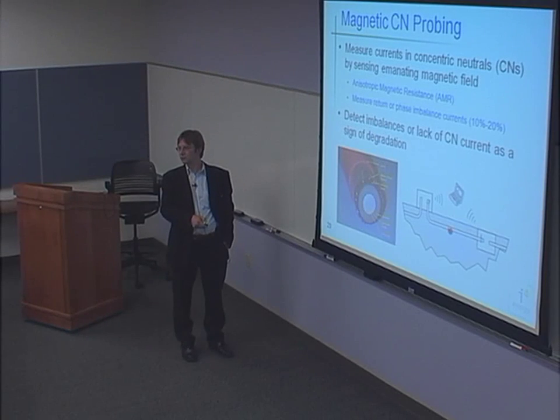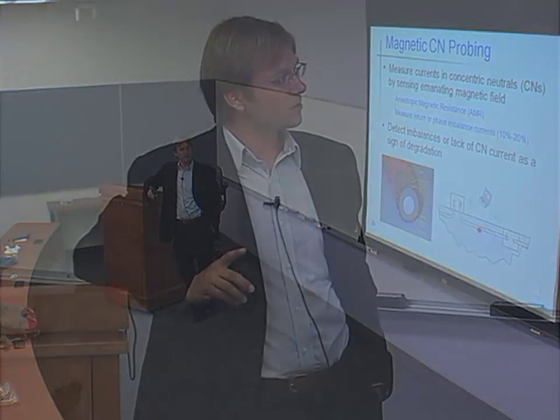The fault current is actually conducted through the entire system down. There is some connection to ground, but that's considered higher impedance. So you really want to have a concentric neutral that goes all the way back to your source, right? You don't want too much current to go through the ground. The fault can then occur anywhere in this concentric neutral, right? As long as you have some concentric neutrals that conduct, that's okay. But I believe if 25% of the neutrals are corroded, the maximum fault current is going to be such that there's just too much impedance and it's going to trip the breaker. So the regulatory threshold, I believe, is 25%. So at 25% corroded, we have to replace the cable. Yeah.